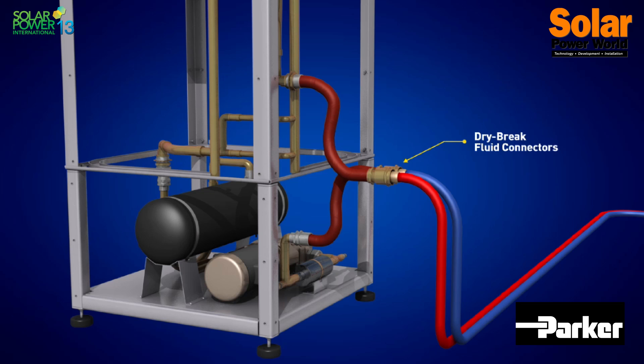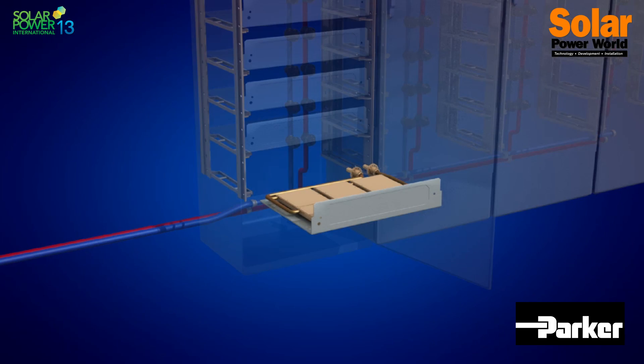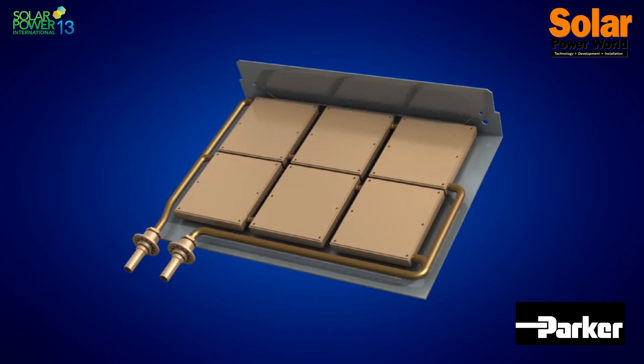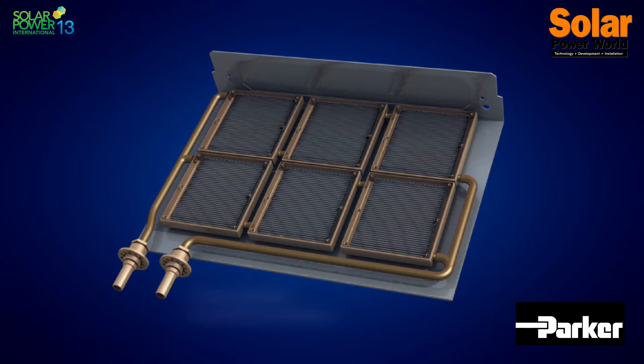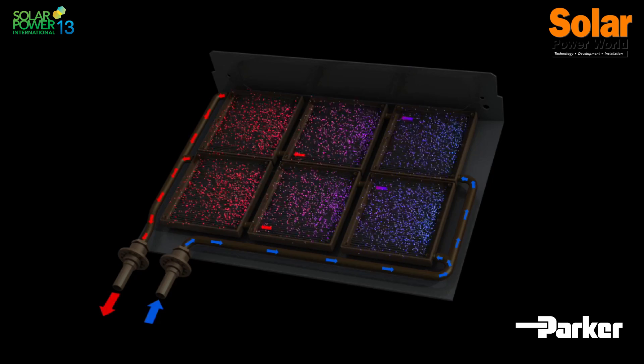When we take advantage of the evaporation, we increase the energy density while reducing your overall operating expenses, because it's a more efficient system. You don't need the same flow rate of liquid, your overall tubing and system gets smaller, and you get three to four times more throughput out of your power electronics.